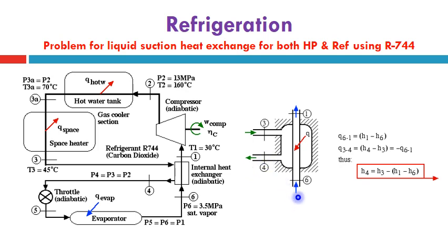However, the suction, which is the outlet of the suction line to enter the compressor and which came from the evaporator, has gained heat from this gas to be cooled at high temperature. So Q61 equals H1 minus H6, such that H1 is higher than H6, and Q removed from the gas side equals Q34 equals H4 minus H3. The equality must hold with respect to the sign convention of the thermodynamic processes, taking into consideration that H4 will equal H3 minus (H1 minus H6).